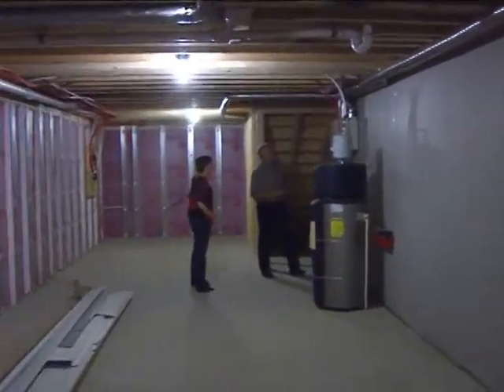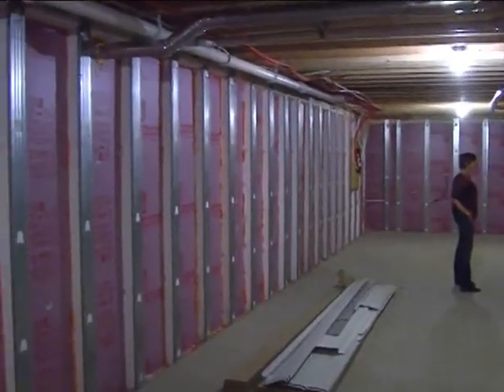So we're bringing outside air in, right, into that white box. At the same time, we're exhausting air out. It's actually going through a heat exchange process where it's crossing in a heat exchanger. So instead of just blowing out our heated air and sucking in really cold air, we're actually exchanging those two air paths through a heat exchanger, and the outgoing heated air is heating up the heat exchanger. The incoming cold air is going through that heat exchanger, recovering up to 50% of that heat from the outgoing stream and bringing it back into the house. We should also mention that the HRV has a filter system built into it to remove air contaminants.